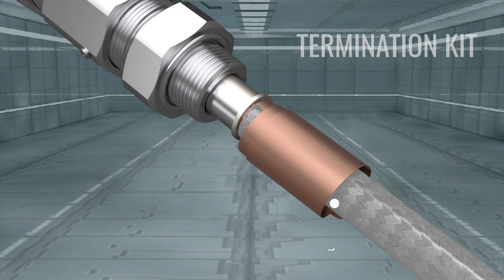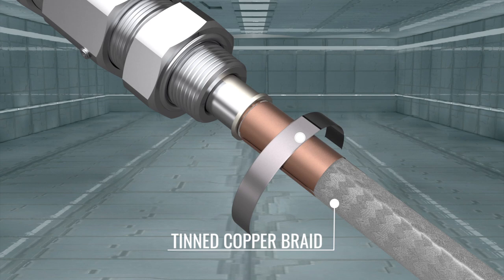Adding termination kits will provide further protection for critical applications. Tinned copper braid is secured to both ends of the cable's exposed inner copper tape and reinforced with a stainless steel constant tension spring clamp.